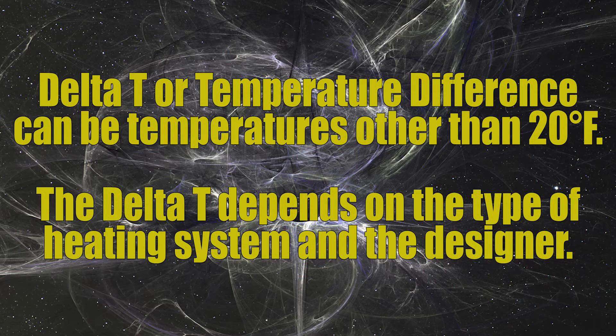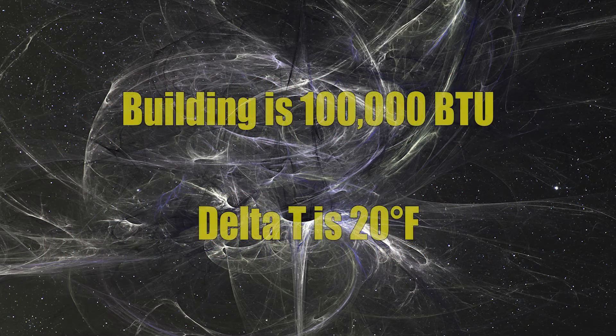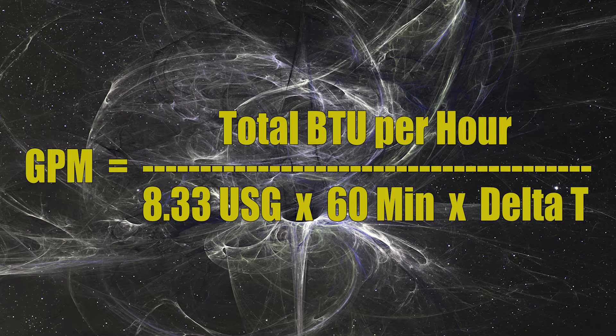Just to be clear, boiler systems do not need to be run at a 20 degree Fahrenheit temperature difference — that's just my example. Many systems use less than that; it depends on the type of system being installed and the designer. So once again: I've got a 100,000 BTU building, a delta T of 20 degrees Fahrenheit, and now I get to plug those numbers into this formula.